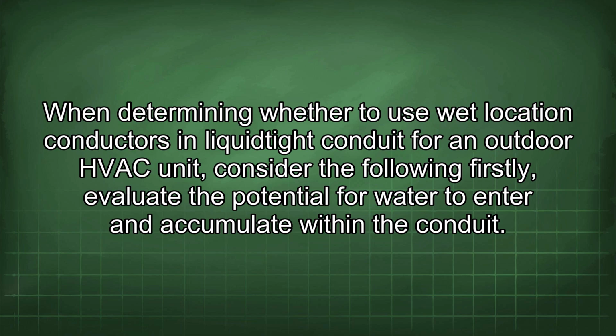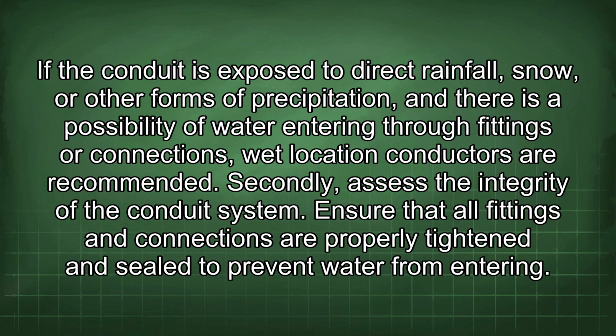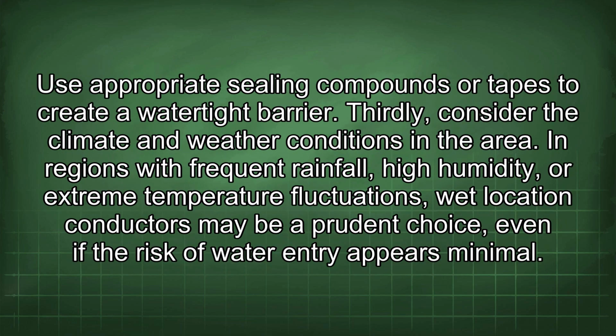Firstly, evaluate the potential for water to enter and accumulate within the conduit. If the conduit is exposed to direct rainfall, snow, or other forms of precipitation, and there is a possibility of water entering through fittings or connections, wet location conductors are recommended. Secondly, assess the integrity of the conduit system. Ensure that all fittings and connections are properly tightened and sealed to prevent water from entering. Use appropriate sealing compounds or tapes to create a watertight barrier.